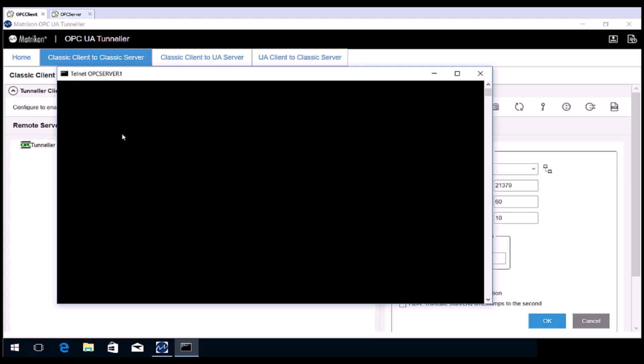If the Tunneller SSC service is running on the OPC server computer, and the specified port is open, you will see a black window with a flashing cursor up the top left. If the port is blocked, perhaps by a firewall, an error will be returned. Note that an error may also indicate that the Matrikon OPC Tunneller SSC service is not running on the remote computer, or has been configured to listen on a different port.